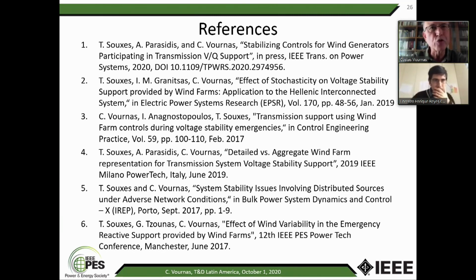Yeah, okay. The one thing is to convince people to use this, and this requires a change in the codes. The codes, remember, they started saying that all distributed generation should be unity power factor. Then they said, no, they have to give some reactive support based on the voltage. Then they also have to have low voltage ride through. Now we have to go to the next step, which is to allow for a system where you give something to the wind producer, so that in case of need, like for instance, if the voltage drops, you get this support. The TSO in Greece, they are convinced, and they are trying to move along this direction.